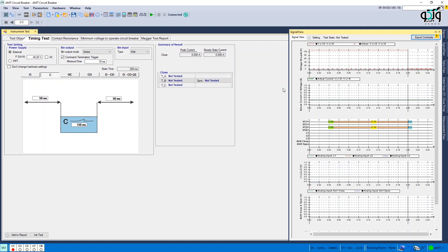Therefore, in case of encountering this error, check the actual current value in signal view. If the actual current reaches 2.5 amperes and the test is stopped, it means that the device is not capable of injecting the current and an external source should be used.